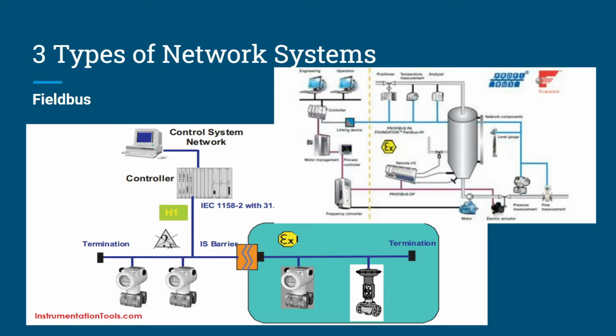This reduces both the length of cable and the number of cables required. Furthermore, since devices that communicate through fieldbus require a microprocessor, multiple points are typically provided by the same device.